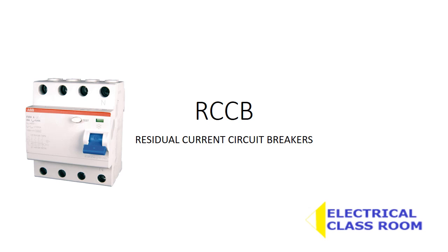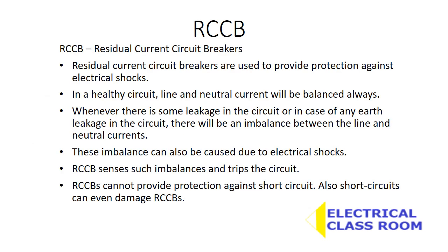Residual current circuit breakers are used to provide protection against electrical shocks. In a healthy circuit, line and neutral current will always be balanced. Whenever there is some leakage in the circuit or in case of any earth leakage, there will be an imbalance between the line and neutral currents. This imbalance can also be caused due to electrical shocks.